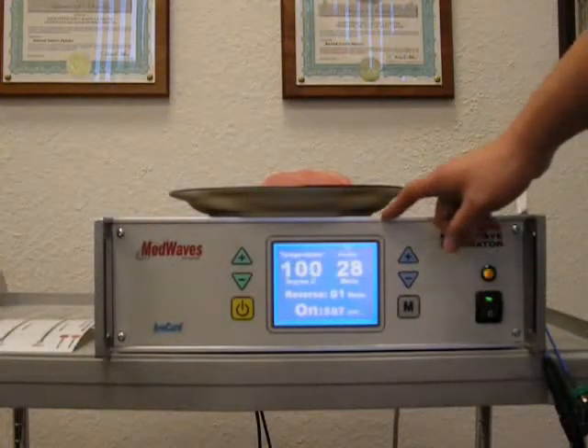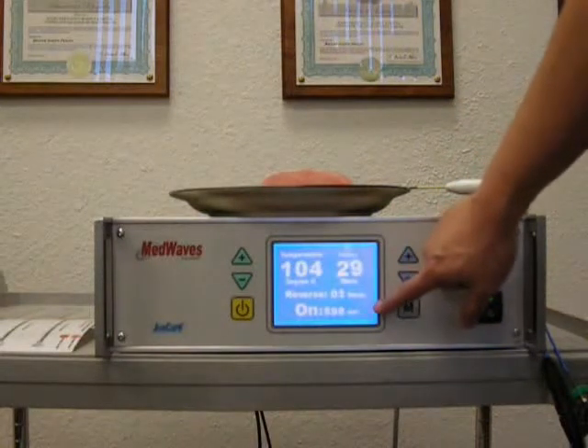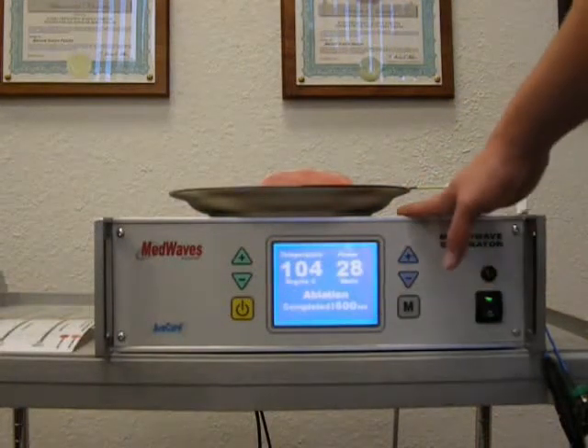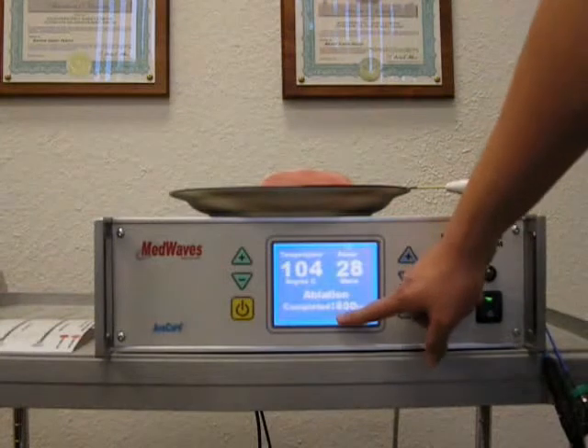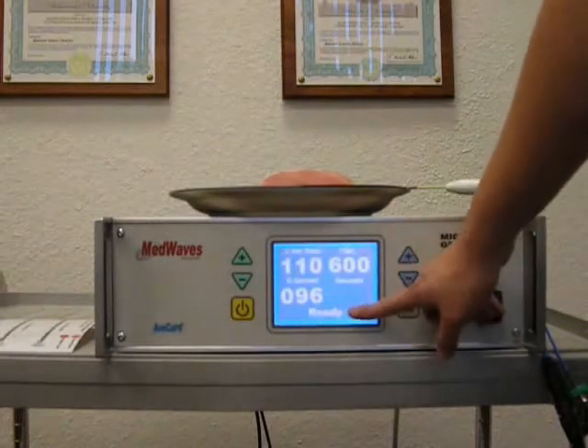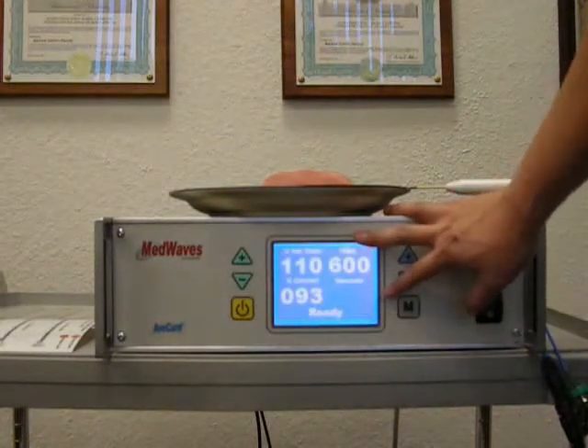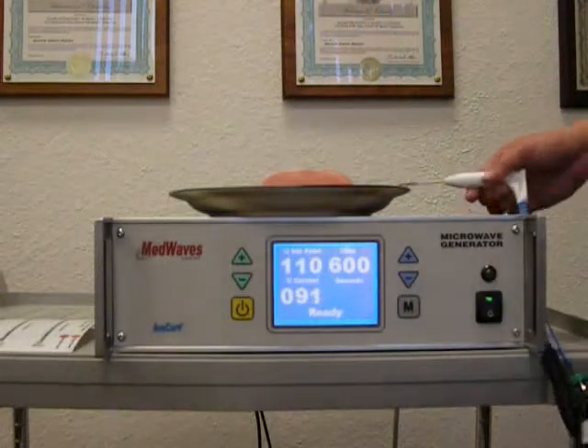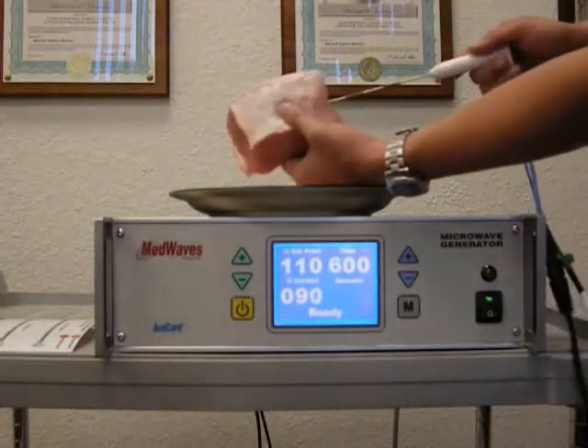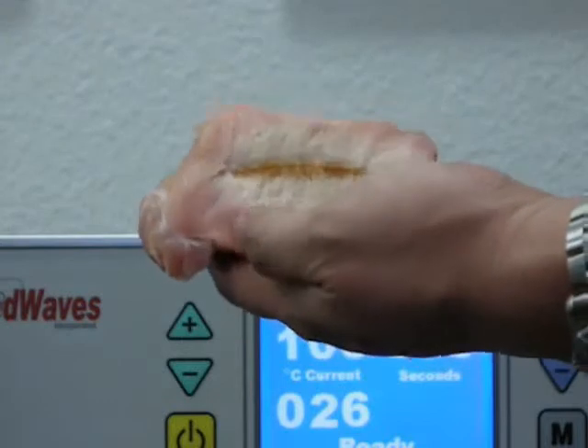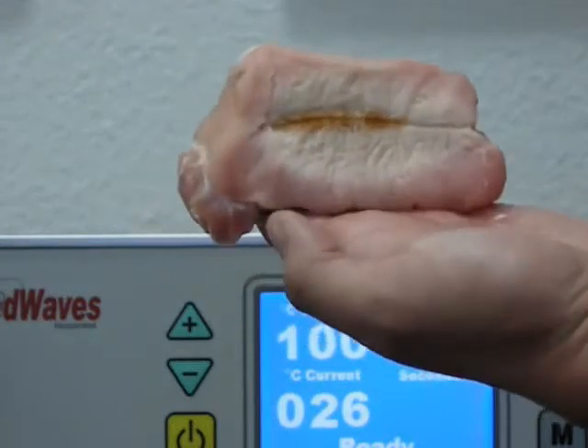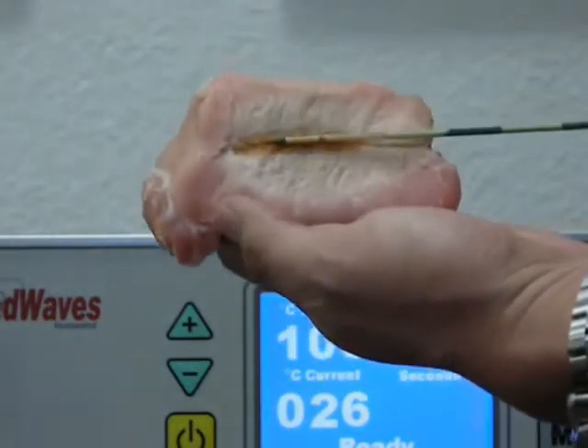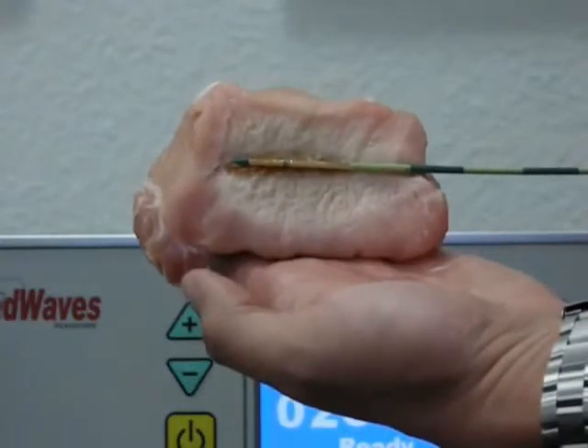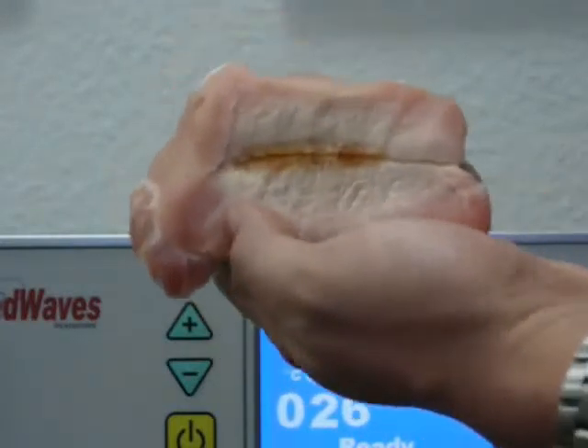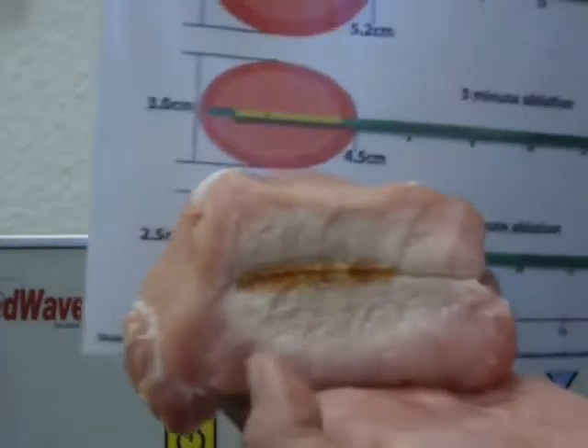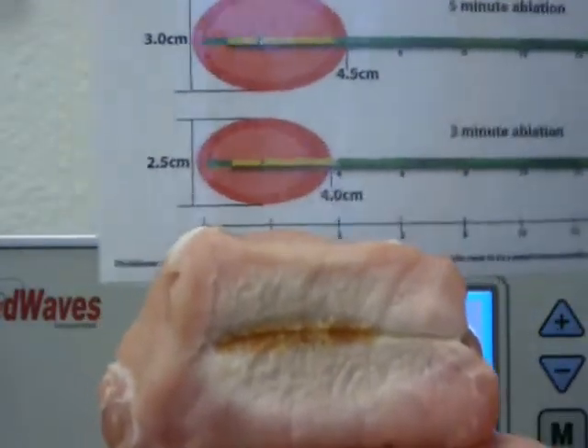As you can see, we're getting towards the end of the ablation. After the ablation is completed, the generator will tell you it's completed, and then it will return back to the ready screen. So afterwards, you can just pull out. Here's a sample of the 10-minute ablation using power control mode. This is where the probe was. And as you can see, the size is very comparable to what you were expecting up here.